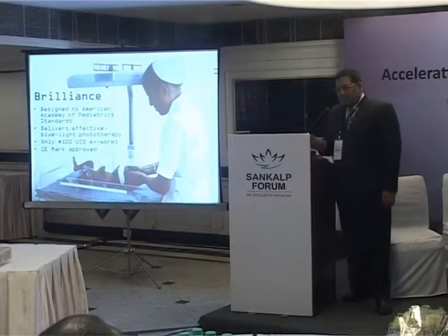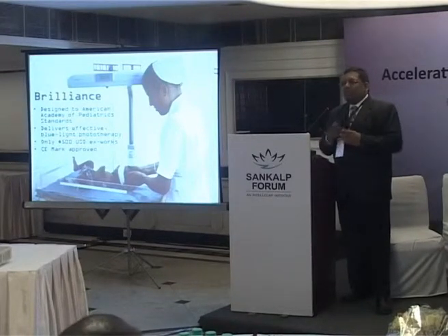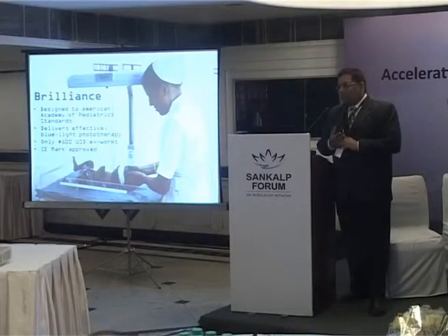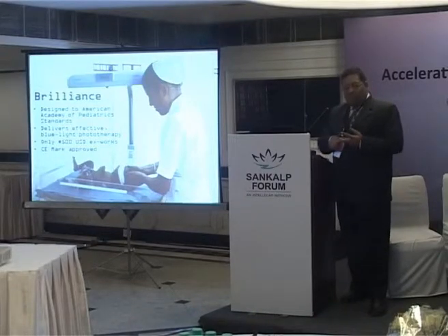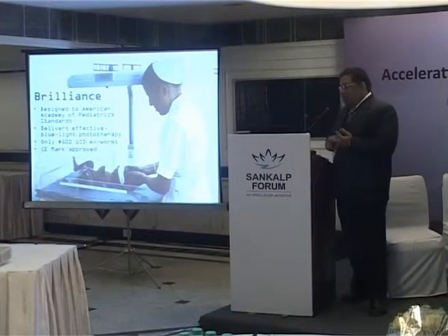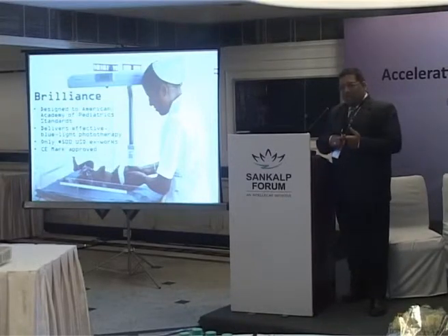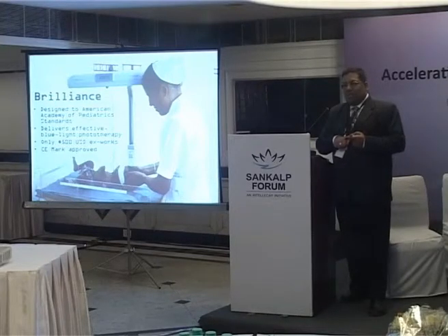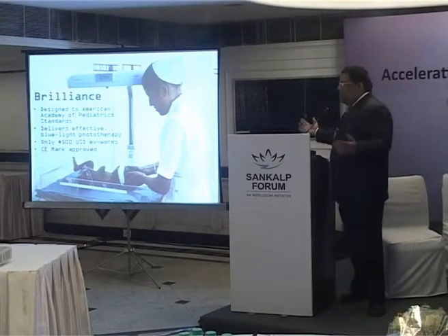What we have come up with is what we call Brilliance, a phototherapy device. Very flexible and feature-rich, it can be used in most environments where this treatment is required — starting with NICUs, to labor recovery rooms, to far-forward clinics where there is no infrastructure. I've seen babies on tabletops being treated. It has very effective intensity and good coverage. Typically one device is used on one baby, but the ground reality is I've seen up to two or three babies under the blue light. This device provides enough surface area to do that, though we do not advise it.